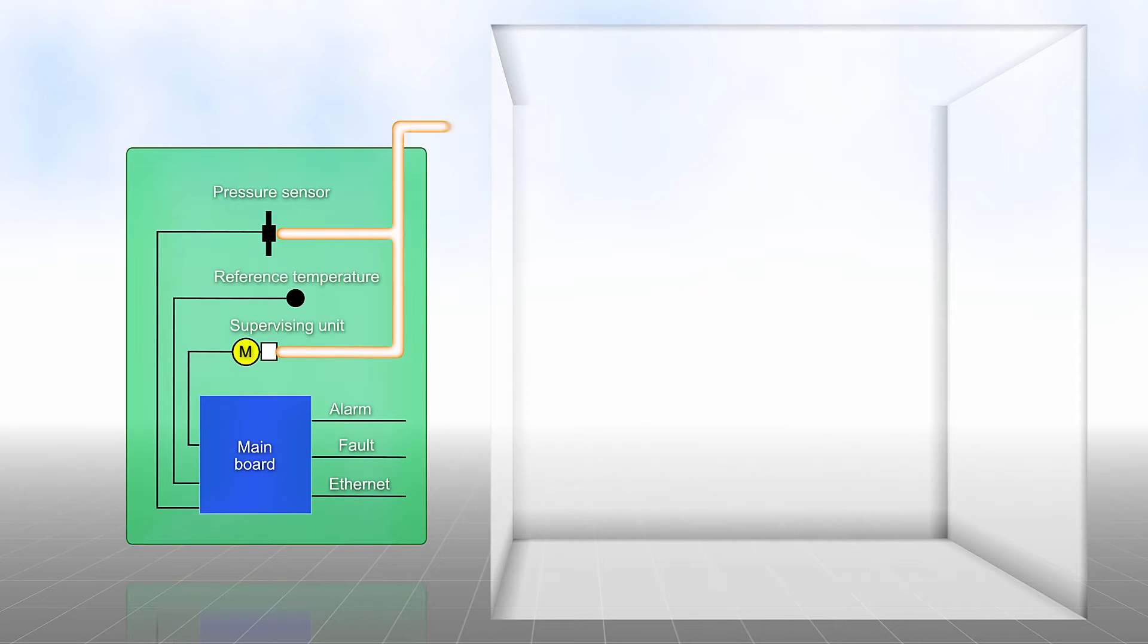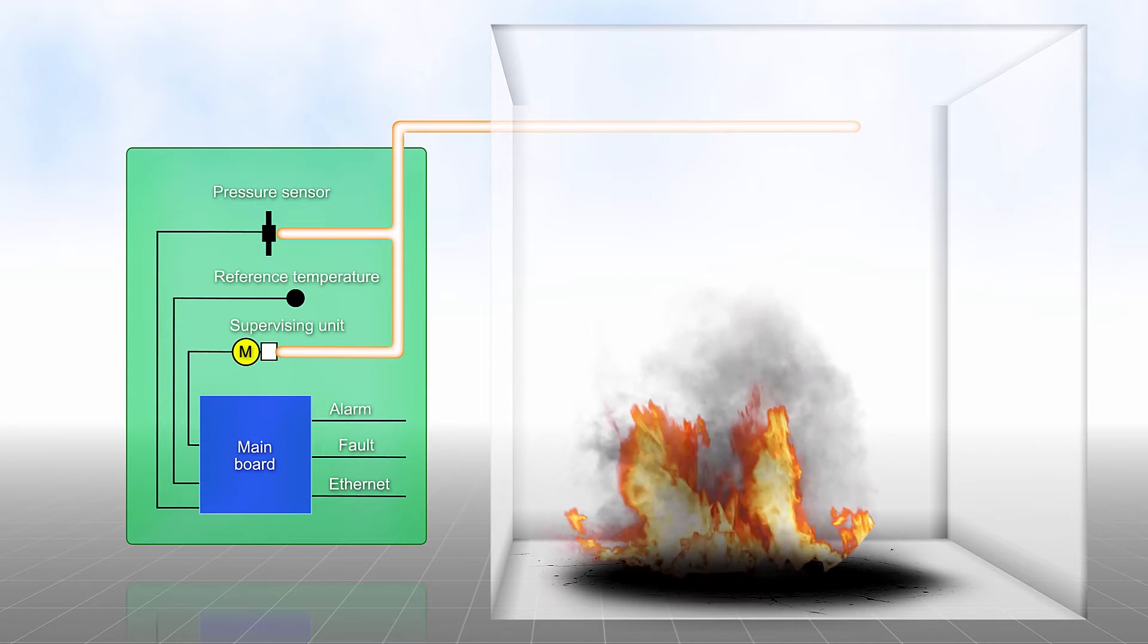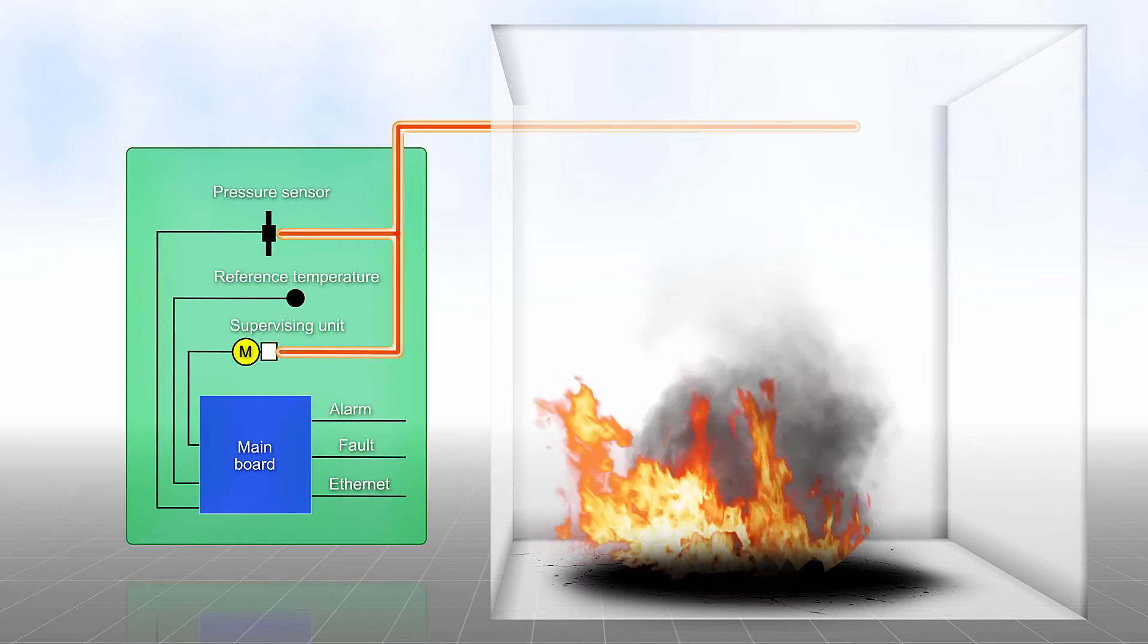The operating principle is simple and reliable. Air-filled sensing tubes are laid in a room to be monitored. If the temperature increases, then the pressure also increases in a closed sensing tube.